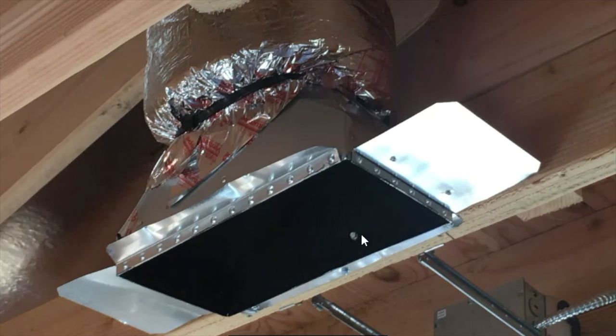in place. Here's another view of another can. You can see how tight the ductwork is. We tape the inside, then we pull the jacketing around and use a 3-foot panduit strap to secure the duct. It's actually secured underneath as well as on top per code.